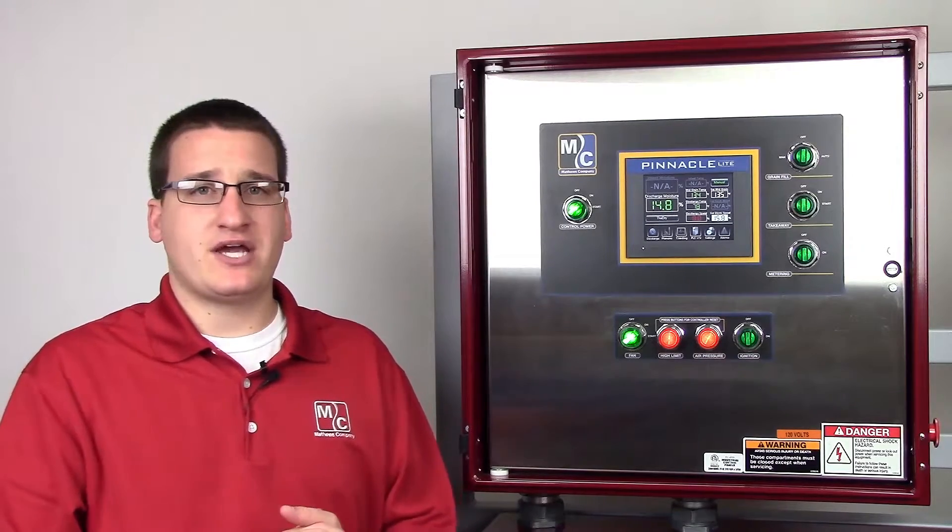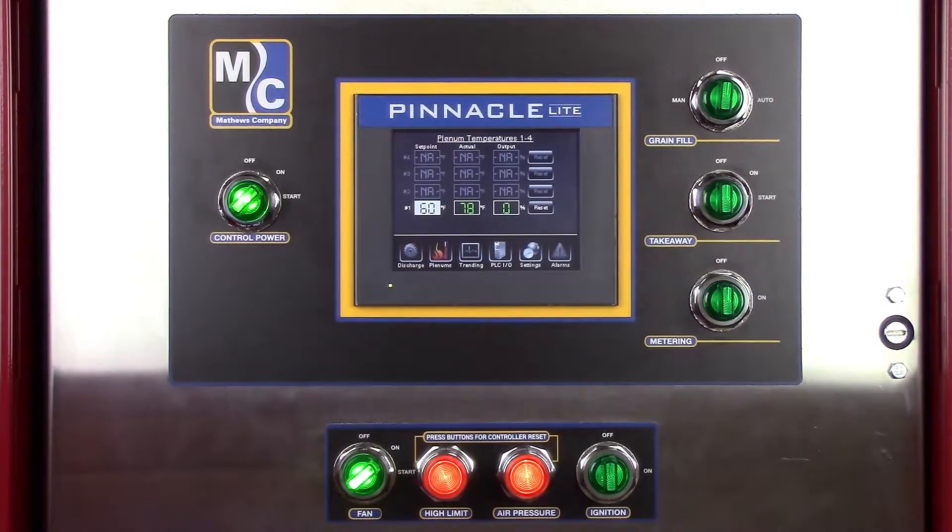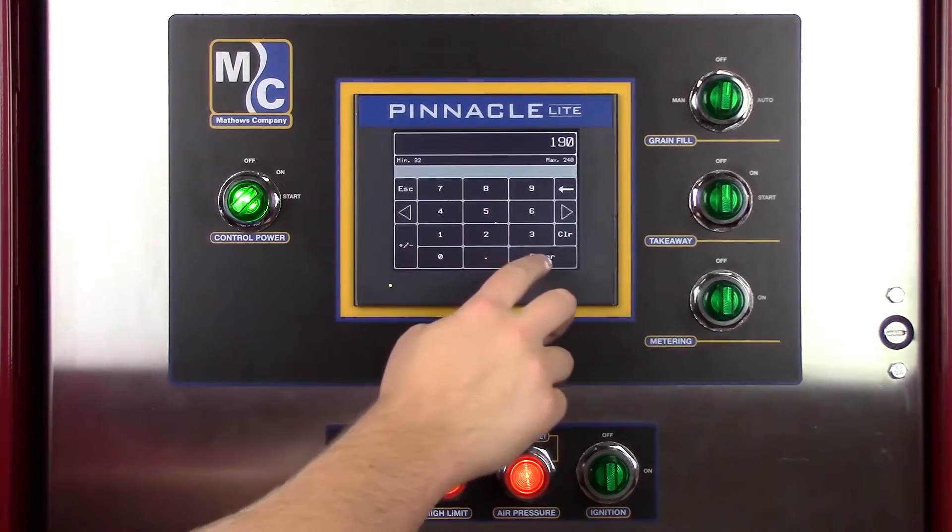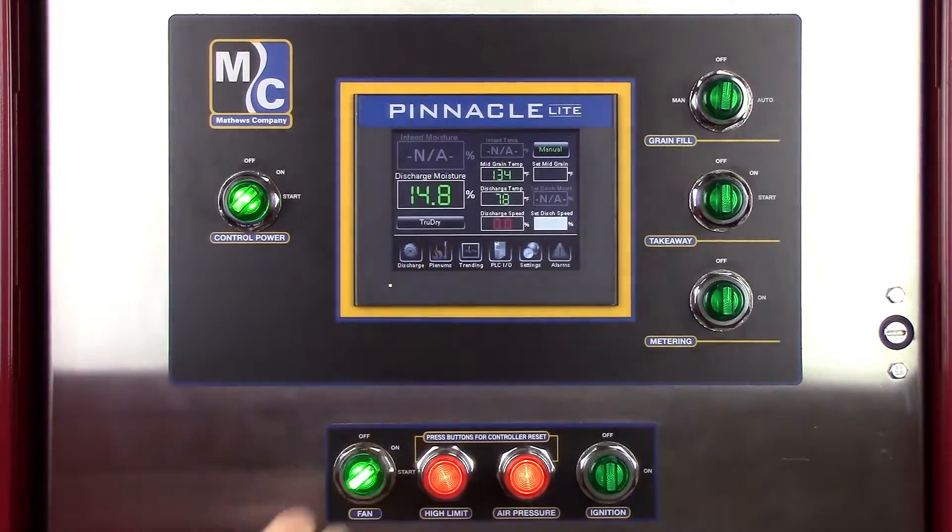Next go to the plenum's chapter and verify your plenum set point. If you're unsure where to set this value, you can check your operations manual for a recommendation.